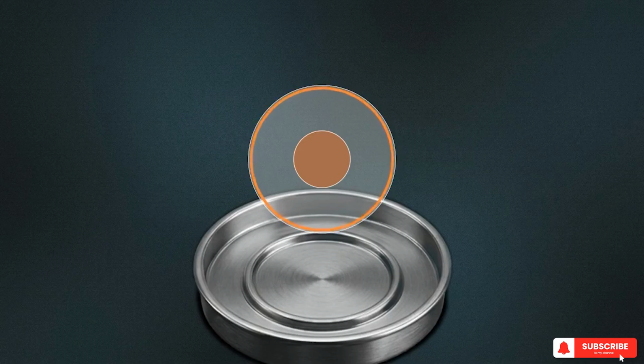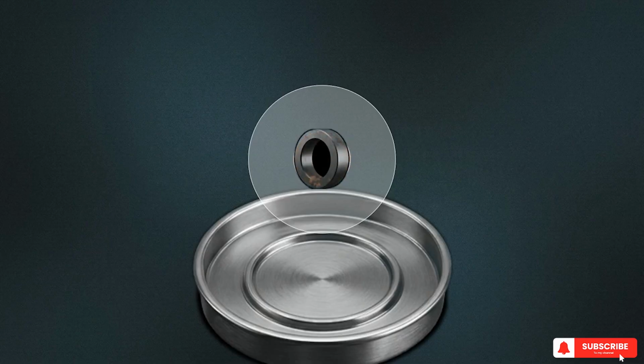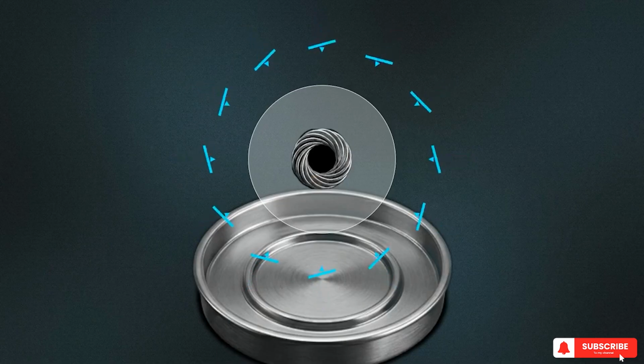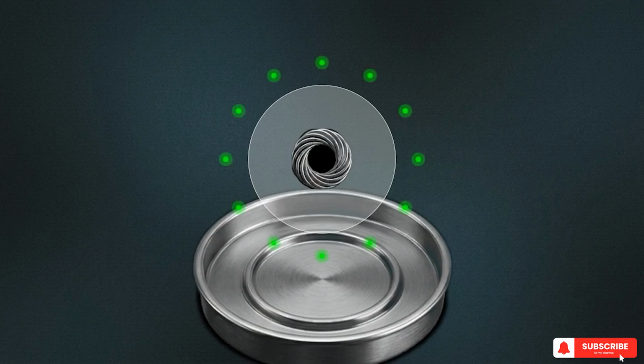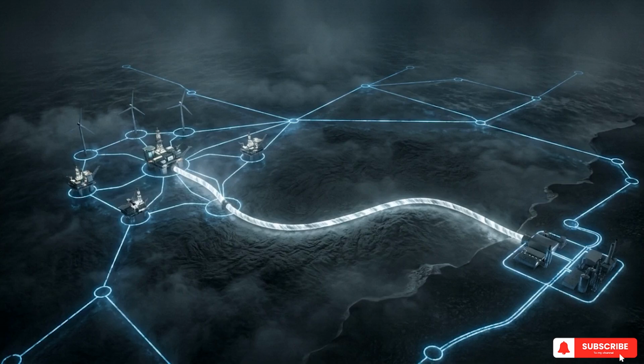Outside of that insulation, the cable has to survive the deep ocean. A dense lead alloy sheath acts as a total moisture barrier, while heavy outer steel armor layers block thousands of pounds of incoming water pressure. Threaded right into this heavy armor are delicate optical fibers, acting as a continuous nervous system, pulsing with data to monitor mechanical strain and temperature changes along every inch of the route. Because most HVDC systems operate without redundant backups, this single, highly engineered wire carries an enormous burden.